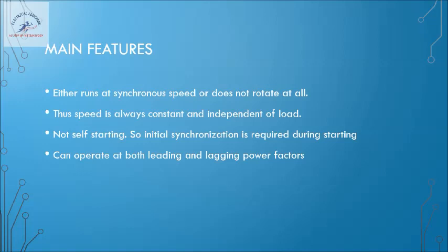So this is one of the advantages: in industry where the power factor is dipping, it is possible to boost the entire plant power factor by using a synchronous motor operating at leading power factors. So along with supplying the industrial mechanical power demand, this will also give us the required reactive power into the system and thus balance the power factor.